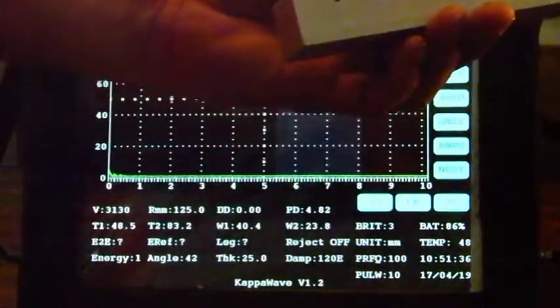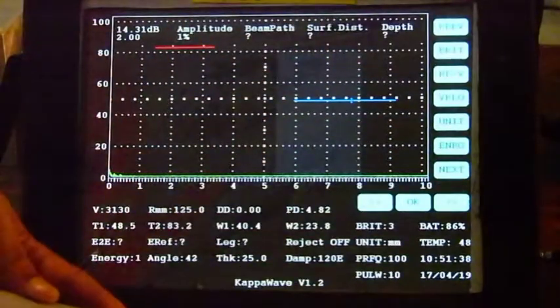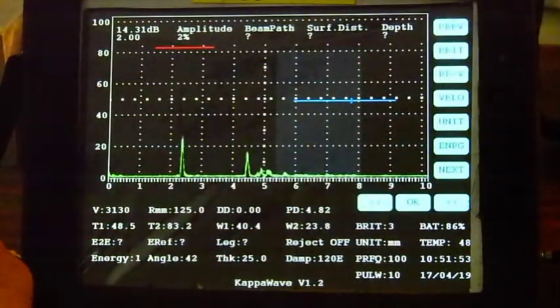The ultrasonic instrument would give you the beam path, surface distance and depth in the case of an angle beam test of a component like this. The same method can also be used for weld testing.